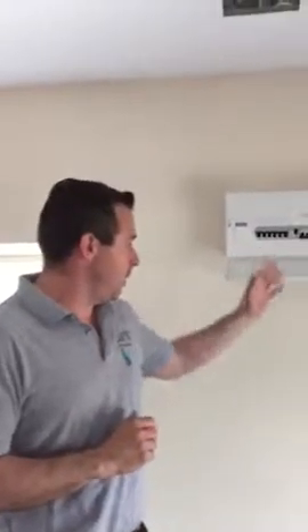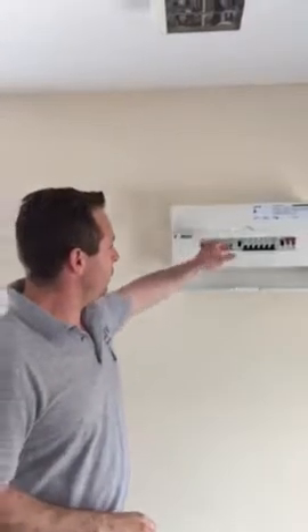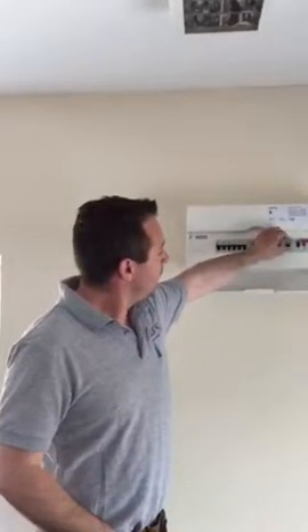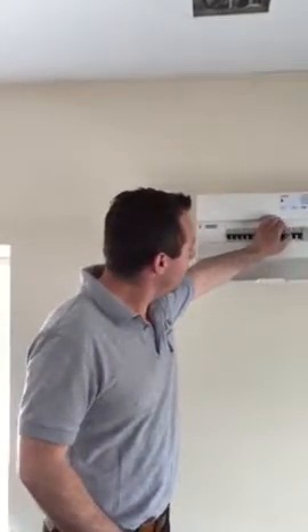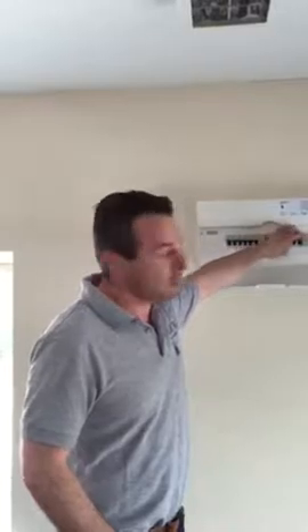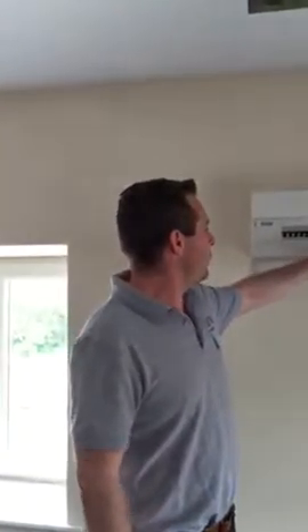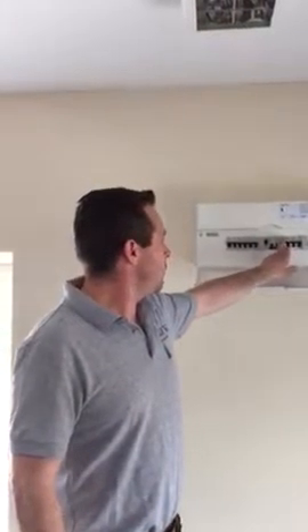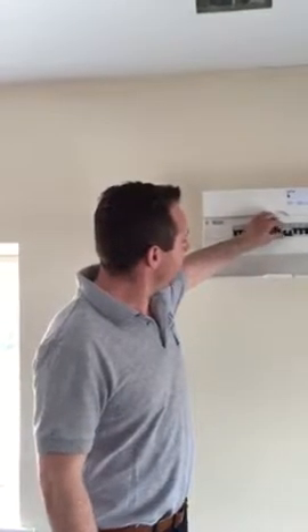But generally, once you turn all the circuit breakers off, the RCD will stay on. Then simply turn each circuit breaker back on one by one until you reach the one that trips it off. Now you know it's that circuit breaker - turn that one off, turn all the others back on, and there you go, it stays on. Your fault is now isolated to just one circuit.